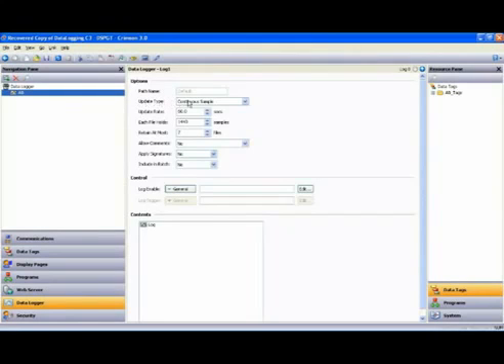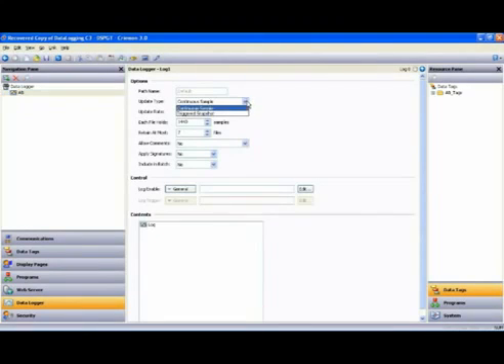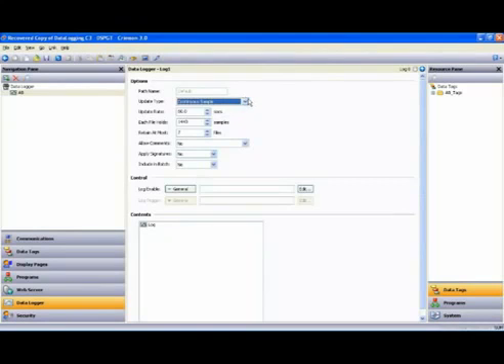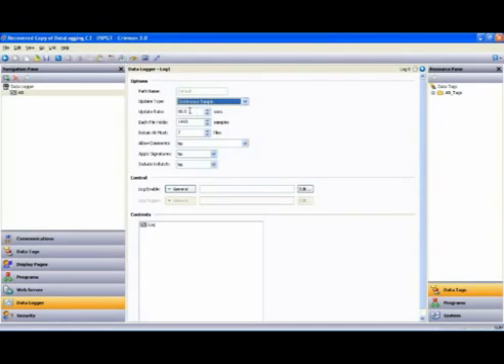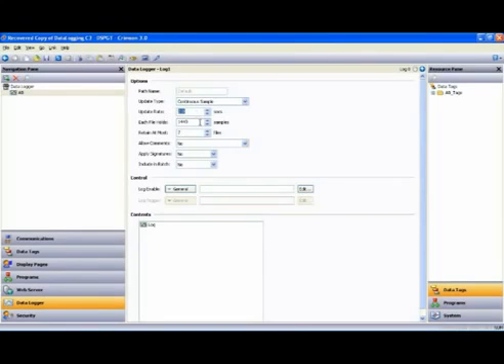Looking at the options for this log, you'll see two update types. You'll notice continuous sample, which allows the user to program the rate at which the samples update, or triggered snapshot, whereby you specify an event or condition that causes the logged update on each occurrence of the event or condition. We will use continuous sample. The update rate is simply how often you want to record a sample. Let's make that two. How many samples in each file? Make that 1,800. And how many files do we want to create? Make that 24.